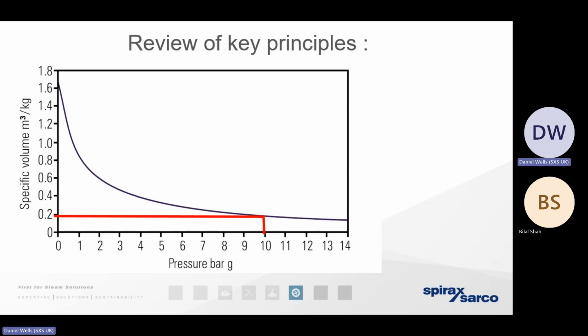Under pressure, the steam's got a much smaller volume. And when we let the pressure down at the heat exchanger, that steam is going to expand significantly. So I want you to think about those steam traps now, because the steam trap is vitally important. It's a critical piece of capital equipment that allows the condensate to drain away and it allows the steam to stay dry. We need that pressure drop across the steam trap so that the condensate can move.